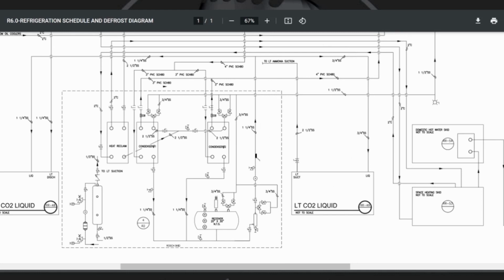Wow. And I see on the top of this receiver, if I had to guess, that's a high level indicator, like a physical one. It's a liquid probe, not high level, just a liquid probe. Okay. There's a funny story about that receiver. We put it in, and we had a real hard time getting the head pressure down to where we wanted it. And it turns out we didn't vent that surge receiver at the time. And the amount of heat in the machine room, we try and keep our machine rooms about 85 degrees. They're air conditioned, but we set it for 85 or 90 degrees. And it was above condensing. And the receiver with the stagnant liquid in it achieved the corresponding pressure, which forced our head pressure up.